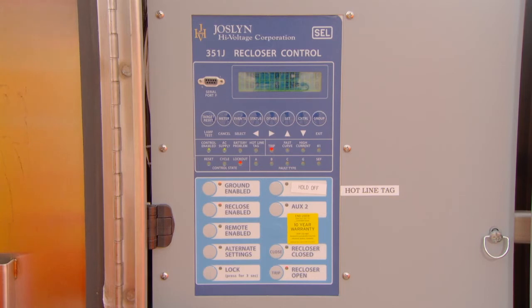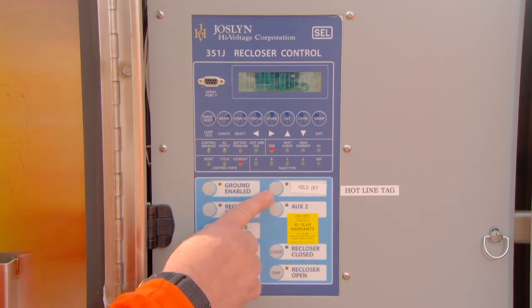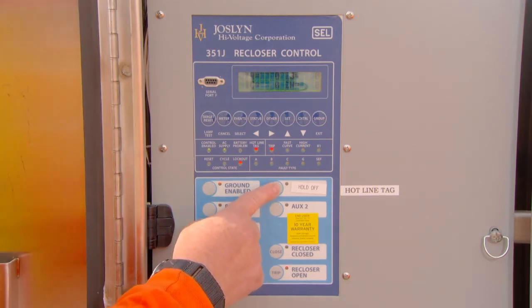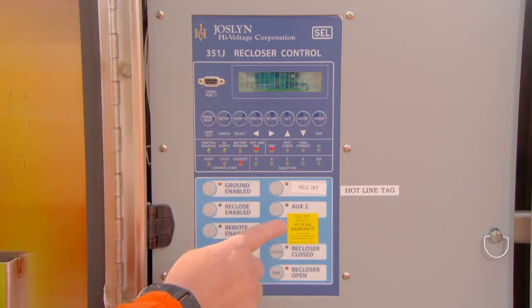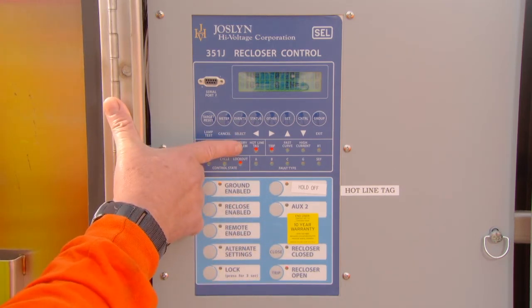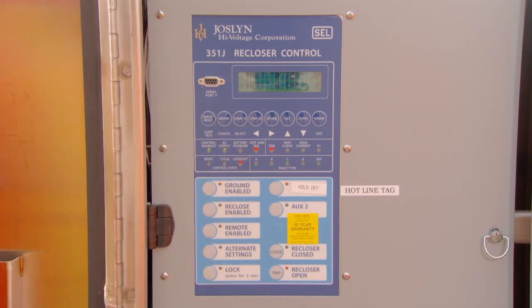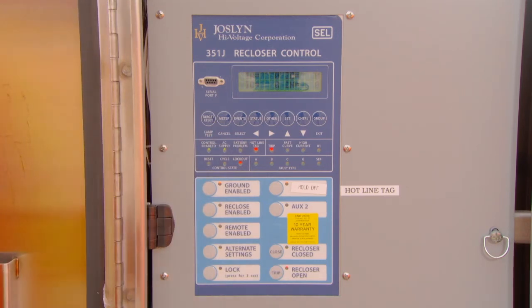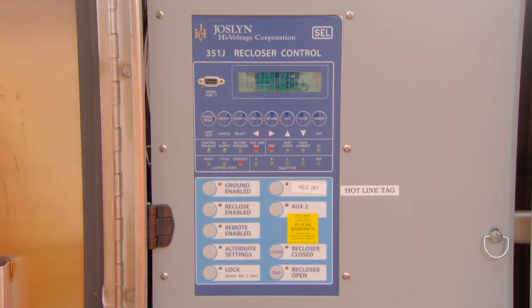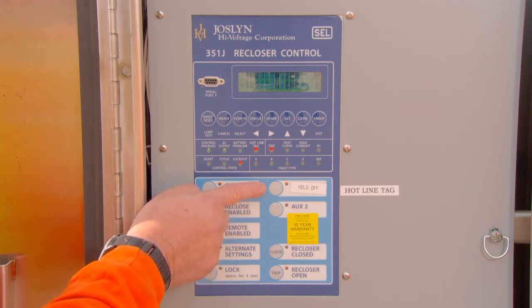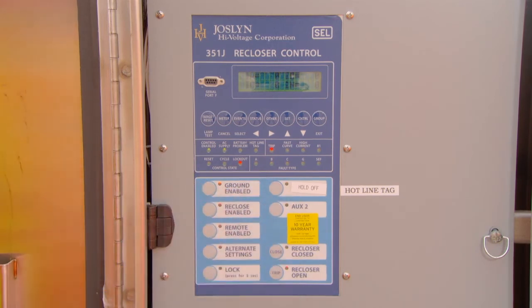Next, we have the hotline tag or hold off button. After pressing this button, its light turns amber, and the hotline indicator LED turns red. We now have a hotline tag or hold off condition on the line. The control will now only operate one shot until lockout using the fast time curve. To remove the hotline tag, press the hold off or hotline tag button again. Both the red and amber indicator LEDs will now turn off.